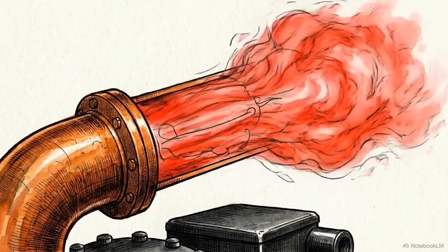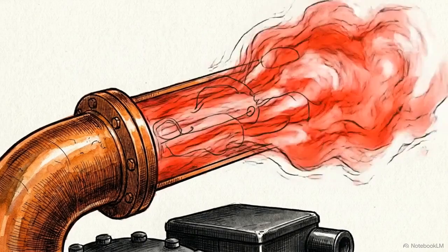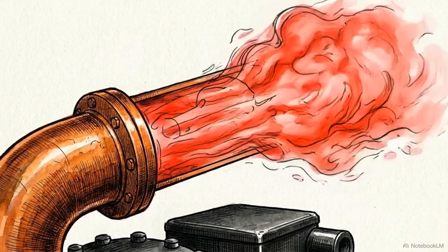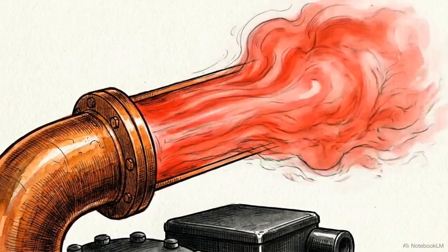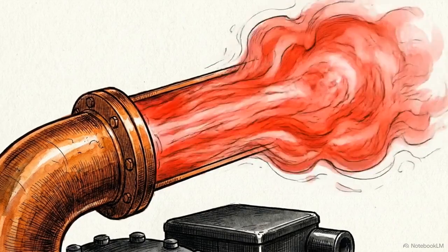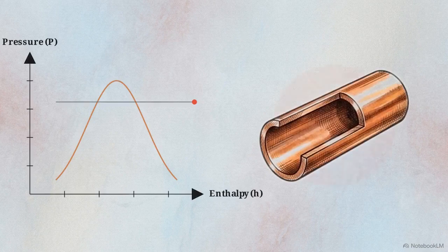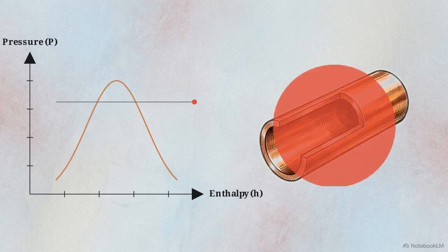To trace that phase change, we follow the refrigerant as it leaves the compressor and enters the condenser. At this point, it is a high-pressure, highly volatile vapor, typically sitting between 70 and 90 degrees Celsius. This split-screen chart illustrates the exact thermodynamic sequence. On the left is a pressure enthalpy diagram tracking the system states, and on the right is a cross-section of our condenser pipe. Heat transfer begins instantly because the 90-degree refrigerant is vastly hotter than the ambient outdoor air or water. Step 1 is desuperheating.